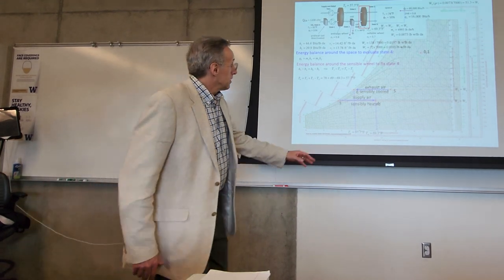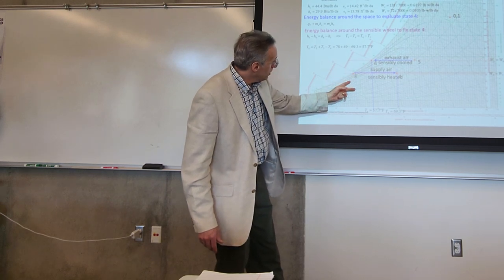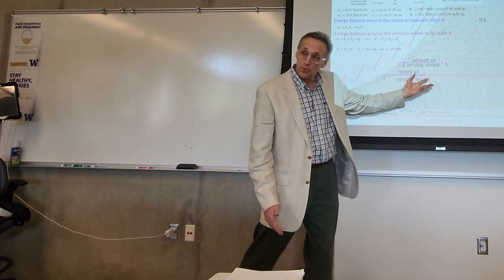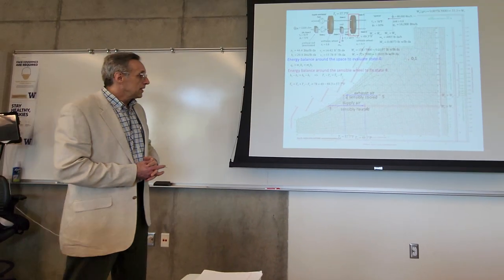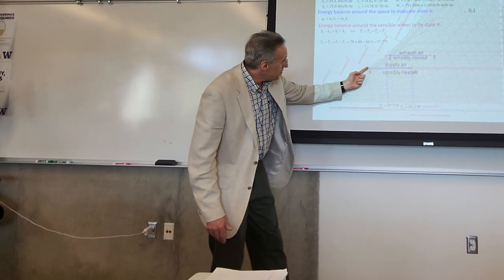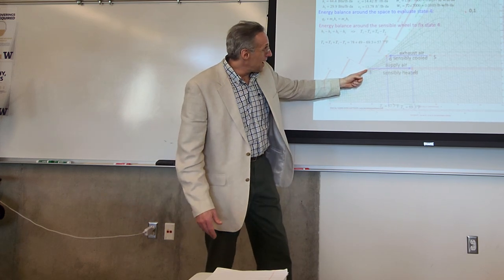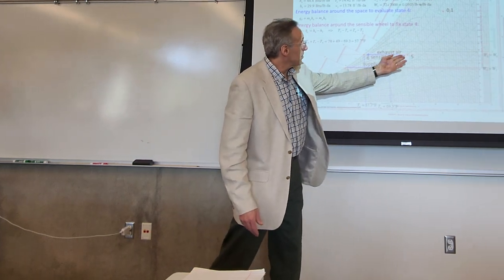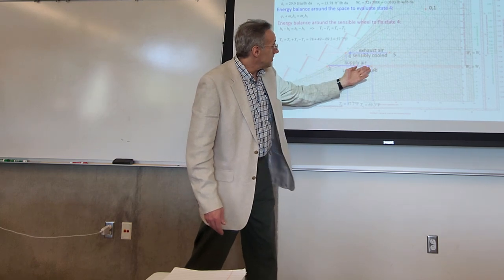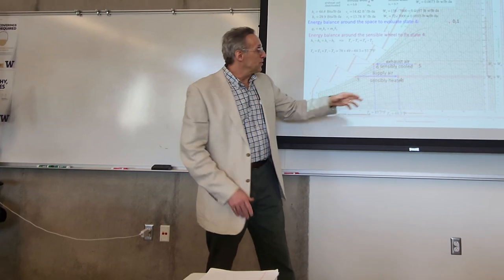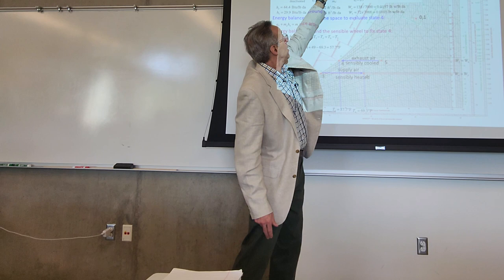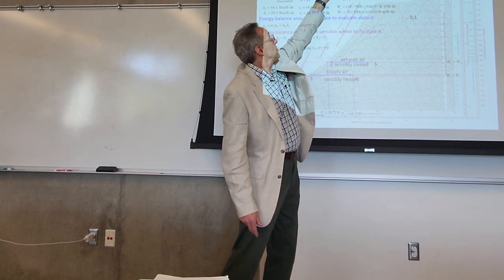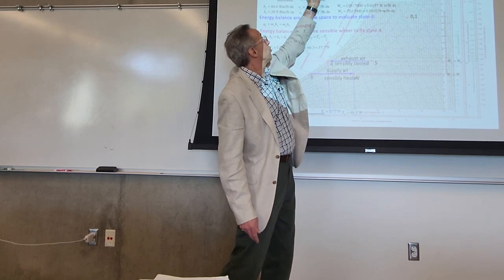So this is our supply air coming off the cooling coil. It's cold, but the goal here is not so much the cooling, it's getting the humidity low enough so that when we put it into the space and it mixes with the air in the space, the humidity is low enough for people to be comfortable in a hot, humid climate. So we don't want to put this air into the space. People are going to be freezing if we do that. And we don't want to reheat with energy, with an electrical coil, because that costs money. So why not just take the return air that's already comfortable and draw some of the energy out of that, and we get a double bang for the buck here, because getting this cooler will help when the air gets over here to the energy wheel, because here we want to pre-cool the incoming air. So when this air gives up its energy to this stream, it actually helps to pre-cool the outside air.